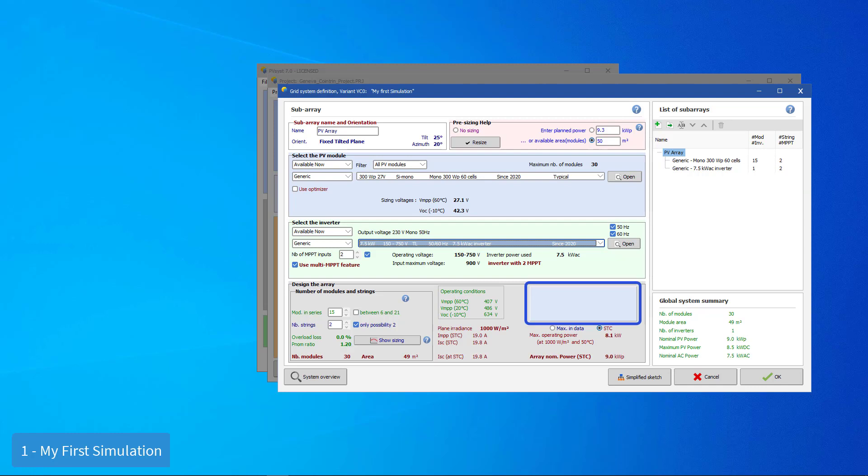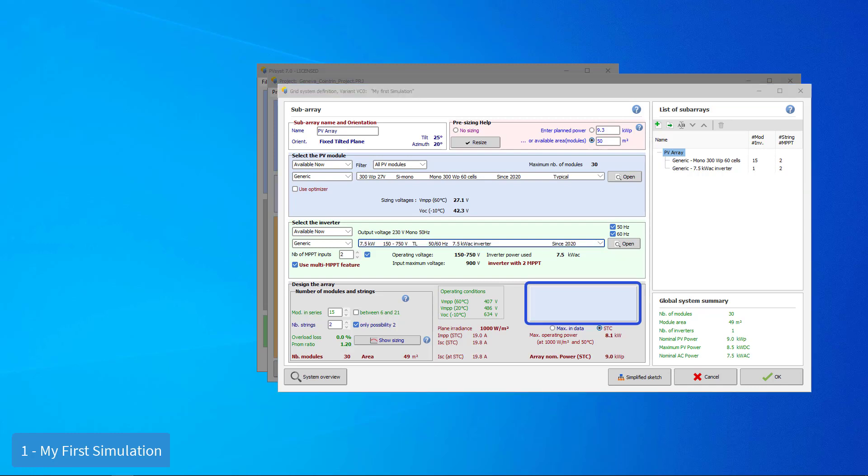Now PVSyst suggests a complete configuration for the system. In our case, this includes one inverter with two strings of 15 modules in series. If you get a red error message, there is a mistake and you have to correct the error. You cannot perform the simulation.